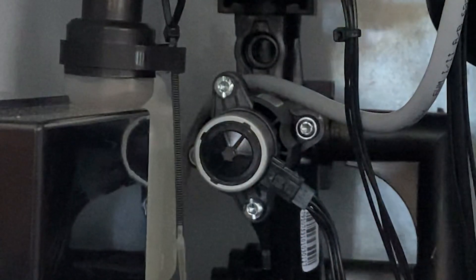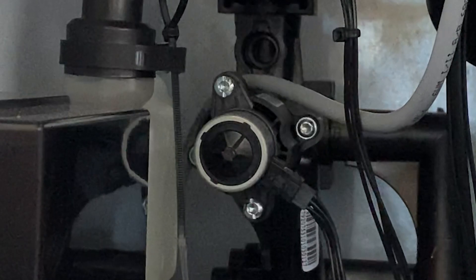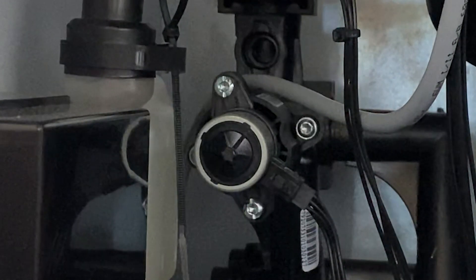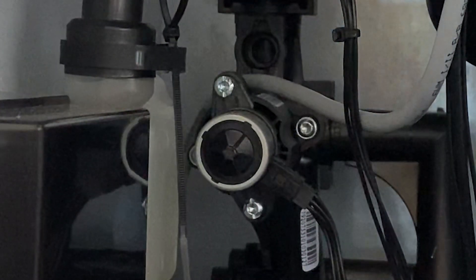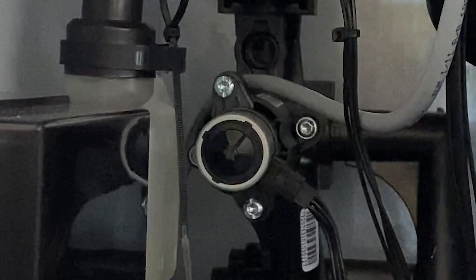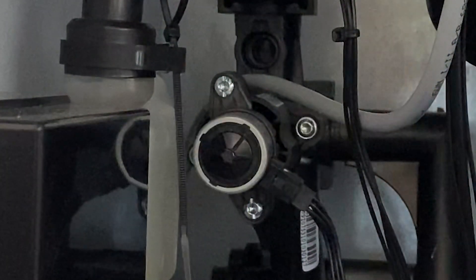And then with the actuator test I can move the valve to heating. And you'll actually see the motor push out a little bit. So proof positive that the linkage is connected and that the valve is moving.